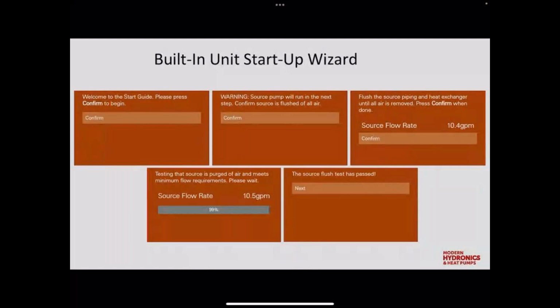And so it won't allow any of the pumps to run or anything like that. It actually has this all built in, and it'll just walk you through step by step. Before we actually fire up a pump, it's going to give you a warning and say, hey, are you confident that you have fluid in there? Make sure that you do before you hit confirm and move to the next step. And then it's going to show you the source flow rate or the load flow rate or domestic hot water, whatever function it's in. It's going to show you live GPM readings on the screen. It's going to go through a flow test. If it fails the flow test, it's going to tell you, hey, there's still air in the system. You need to do some more flushing, and then you can rerun the test. Once the test is passed, you can move on to the next step. It works incredibly well. We've had great success with it, and we've just taken this further with this new unit and its new capabilities. So the startup wizard is a really good feature.